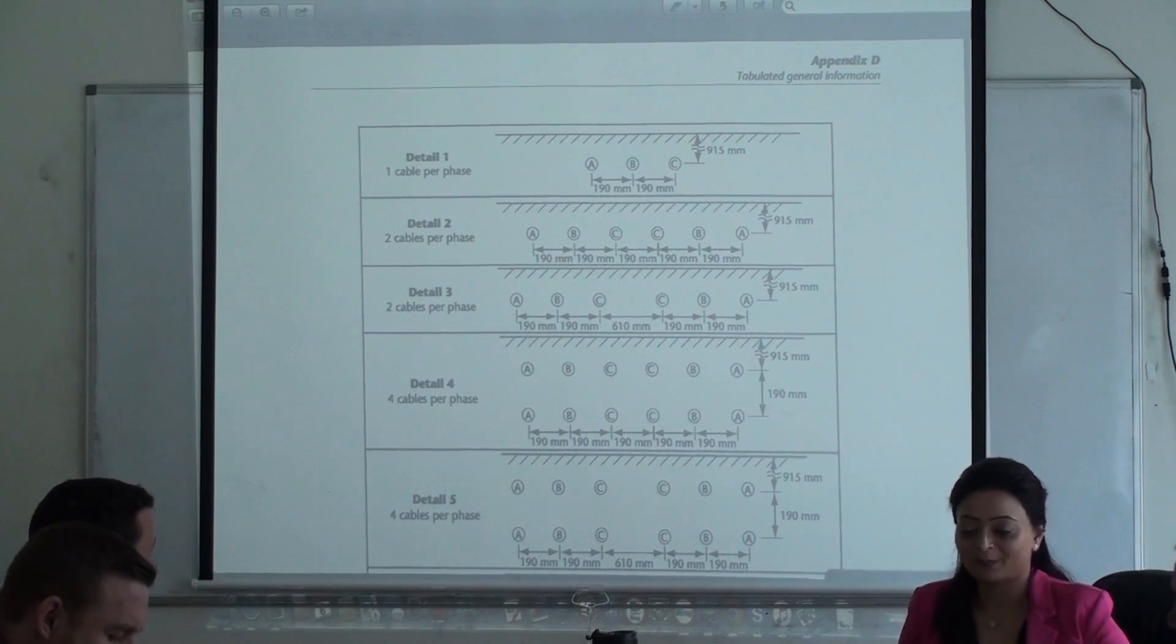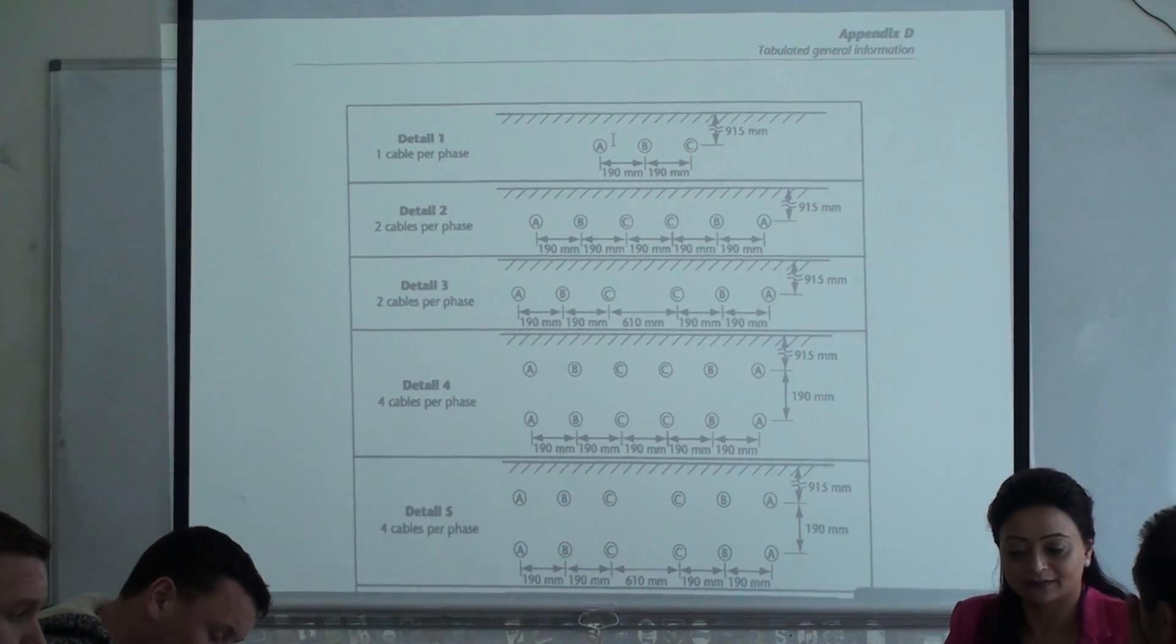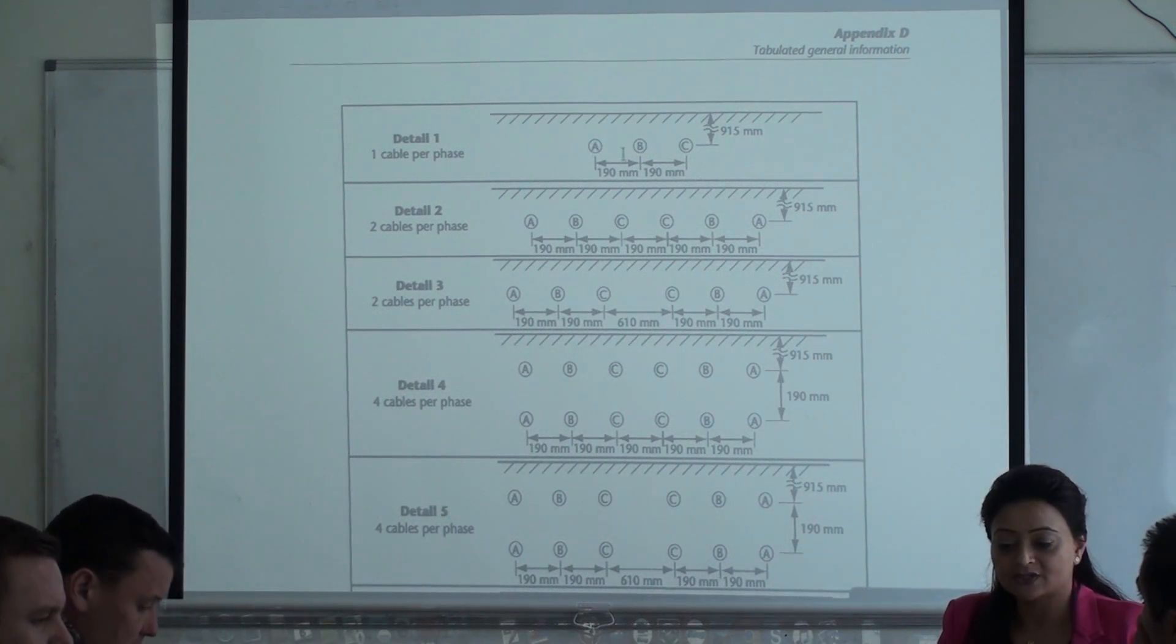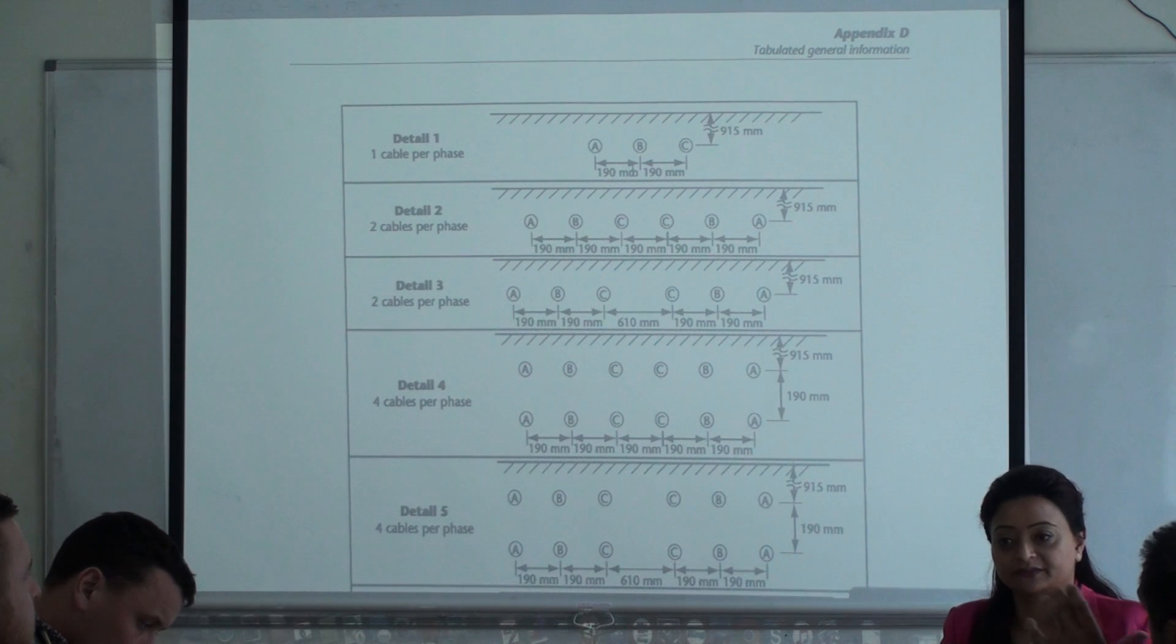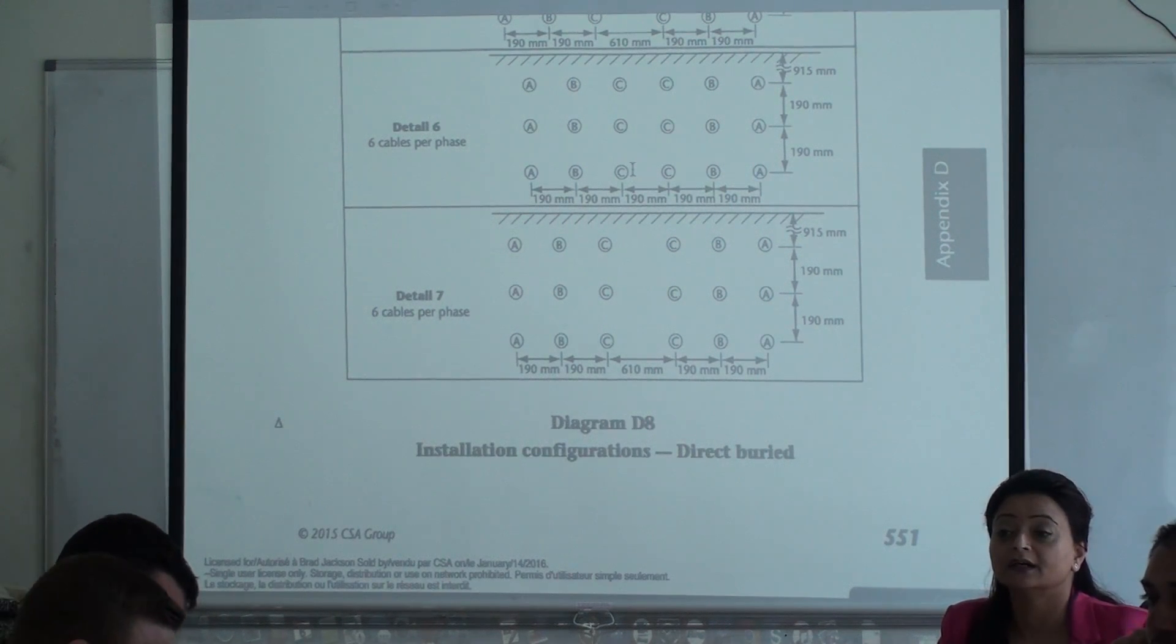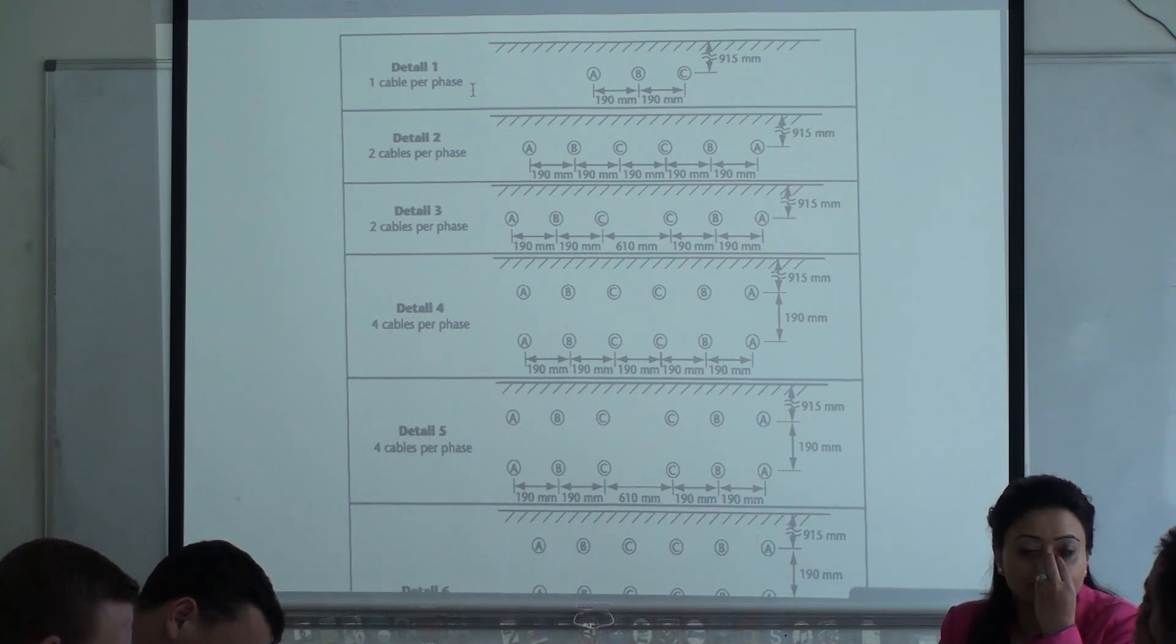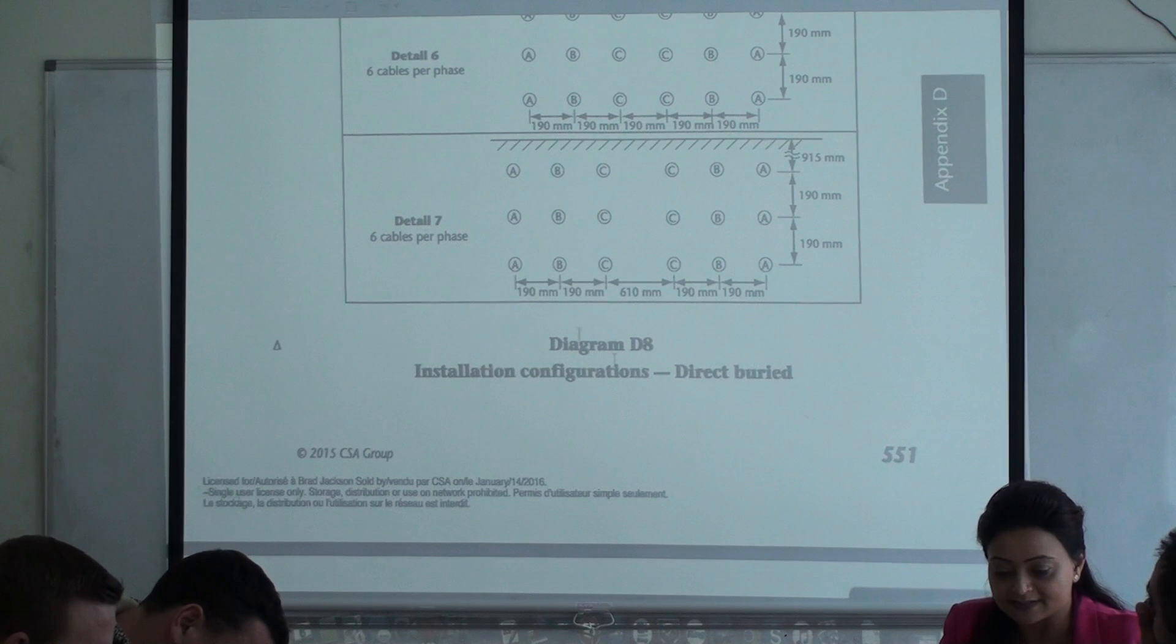Page 551. Are you guys with me on this one? Let's understand this nice looking diagram. If you see the top, this represents the floor level. Your conductors are placed 915 mm away or under the floor level. Circle A, circle B, circle C represents phase A, phase B and phase C wire. They are placed 190 mm from each other. We are on page number 551. Alright guys, so let's say I was told I am installing a copper wire. The keyword will be in your exam directly buried.